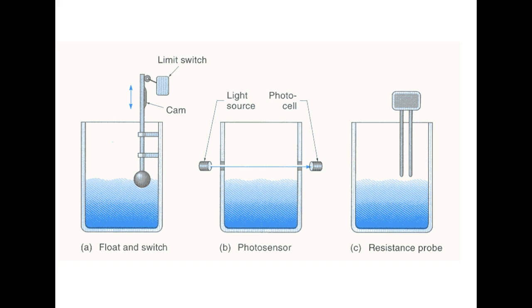So we have a device called a limit switch. A limit switch is basically a switch, like your wall switch over there. We could make the wall switch into a limit switch, just taking some type of operator and putting it out there so when you walk by it, it turns on, and when you go back the other way, it turns off. That's basically what a limit switch is. A limit switch is usually spring loaded, and it's got what we call an operator on it. On this one, they've got a cam.